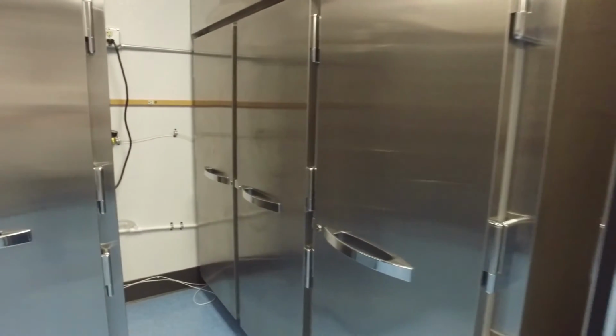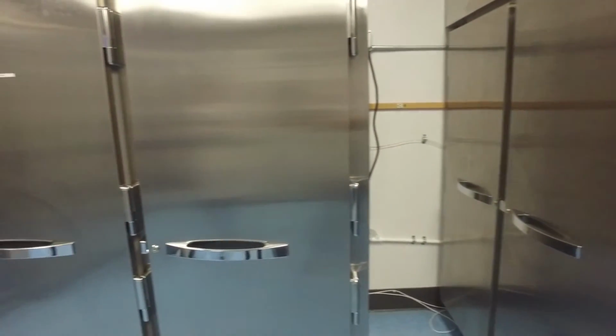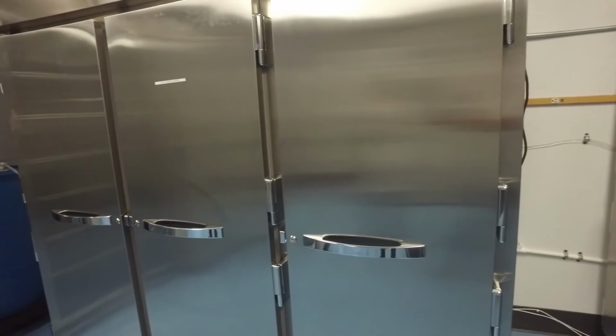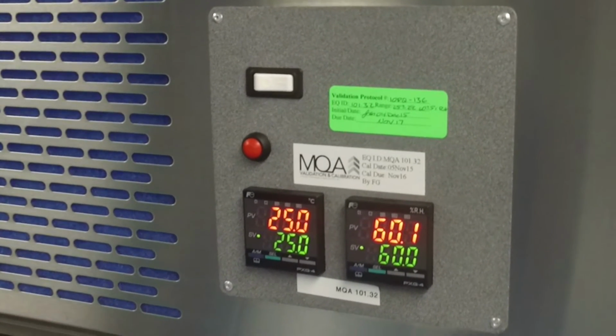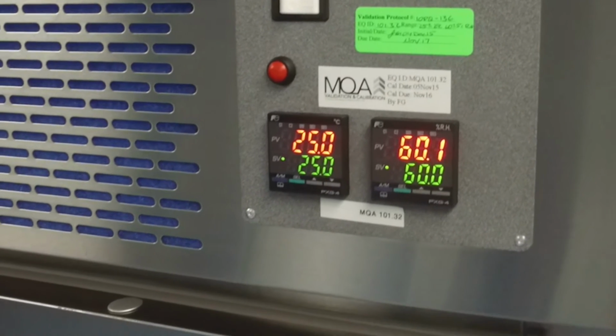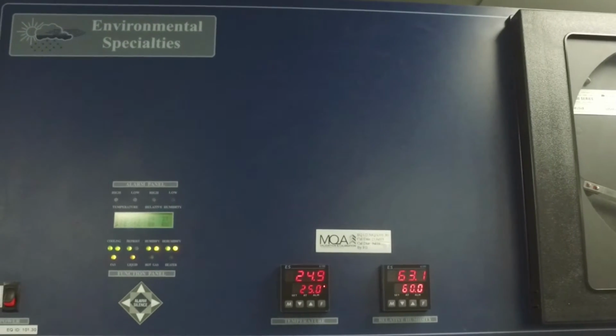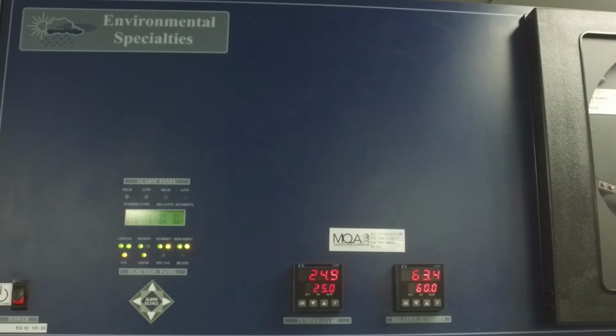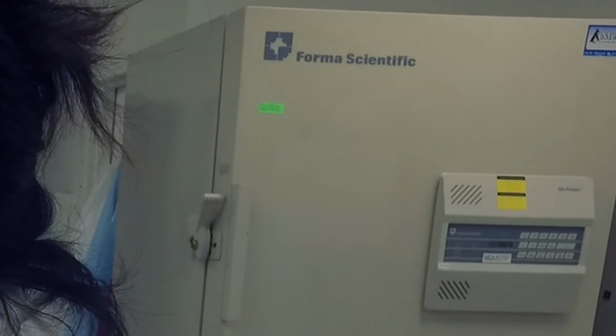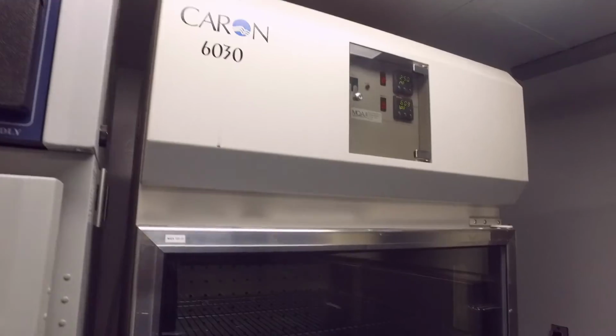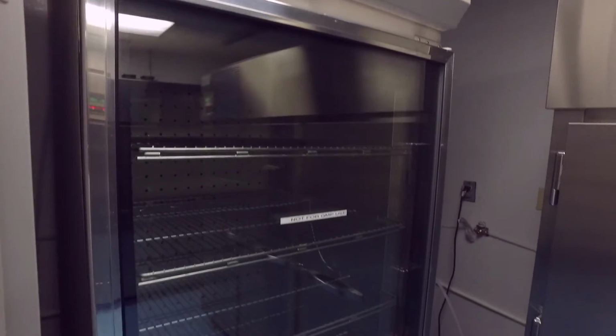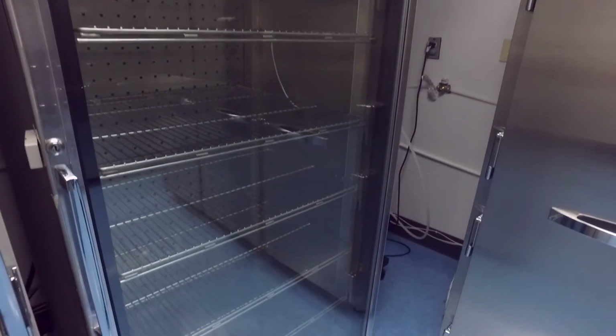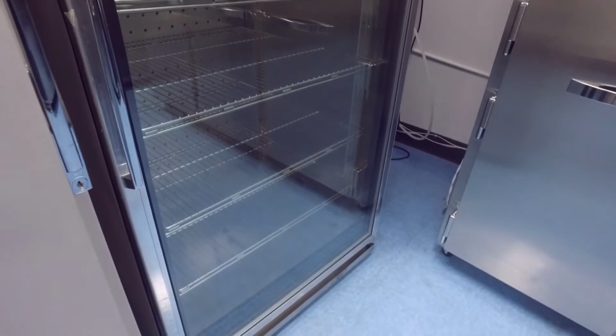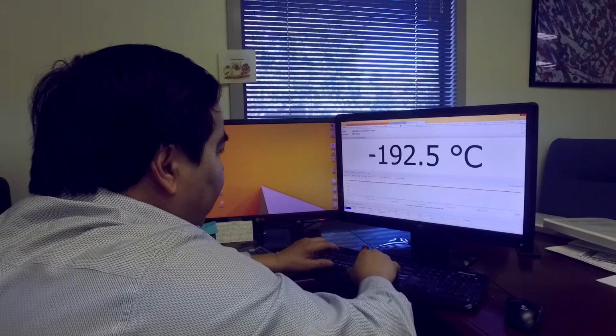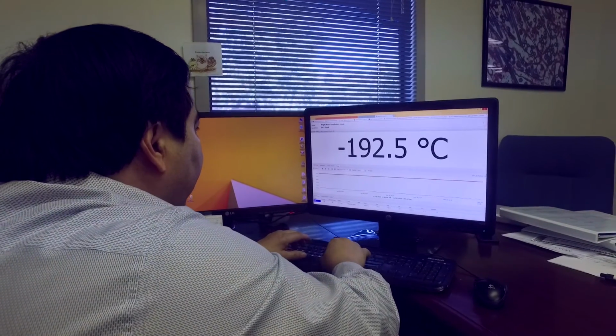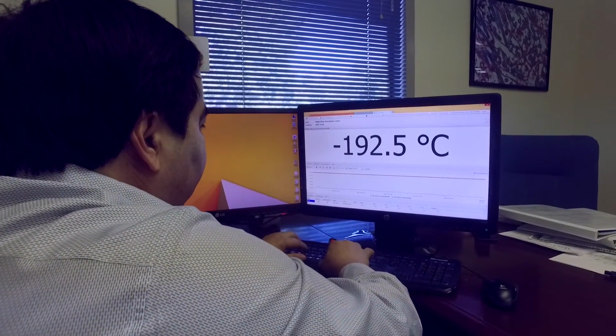We have a dedicated suite for stability chambers and can perform analytical and microbiological testing at various time points according to ICH guidelines. Your samples are stored in validated equipment under a controlled environment. On-site is a backup generator serving the facility in case of temporary power loss, and lab instruments have individual UPS for secondary backup. Controlled temperature chambers are monitored 24/7 by a Vaisala system that notifies lab management of alarm situations.